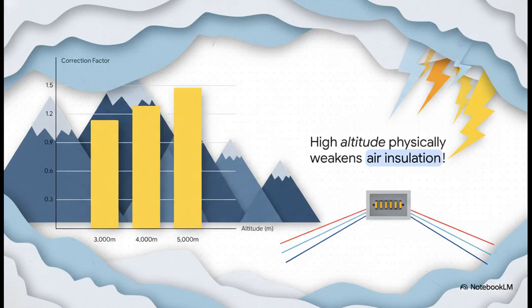And then there's altitude. I absolutely love this fact because it always catches people off guard. High altitude physically weakens air insulation. The air is thinner up there, so it's just less effective at stopping an arc. The IEC standard gives you normal values up to 2,000 meters. But check out these correction factors. If you're installing a panel at, say, 5,000 meters above sea level, you have to multiply your clearance gap by 1.48. That means you need an air gap almost 50% wider just to get the exact same level of safety you'd have down at sea level. If you forget to adjust for this, your high-altitude panel is basically a ticking time bomb.